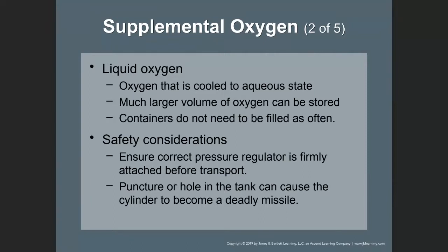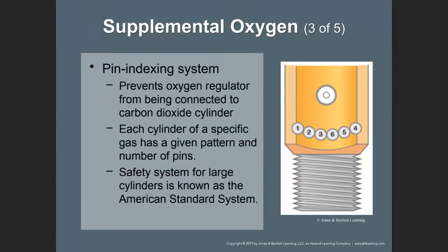Safety considerations. Ensure the correct pressure regulator is firmly attached before transport. A puncture or hole in the tank can cause the cylinder to become a deadly missile. The pin indexing system prevents an oxygen regulator from being connected to the carbon dioxide cylinder.